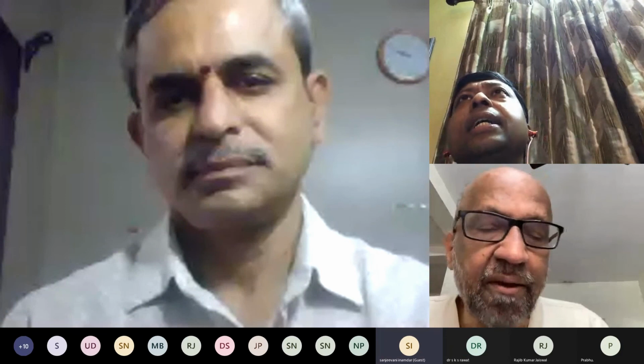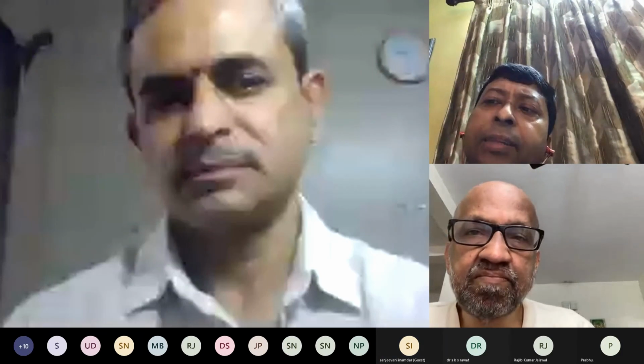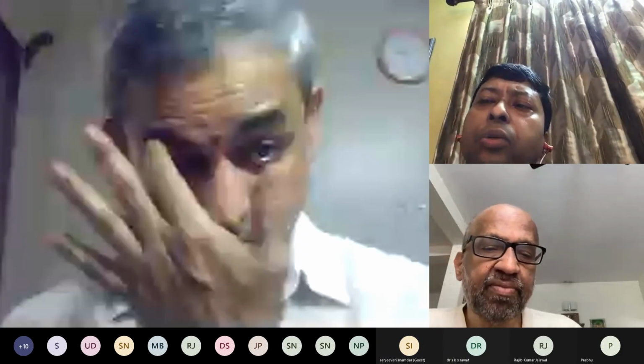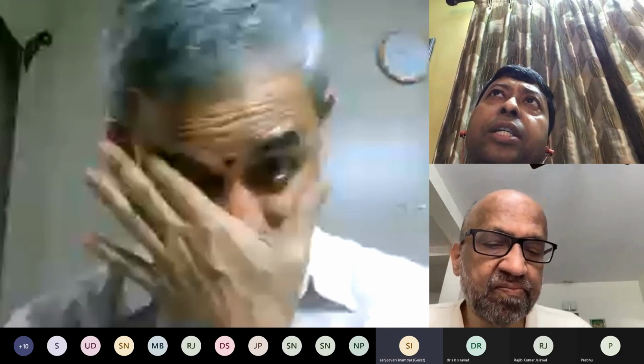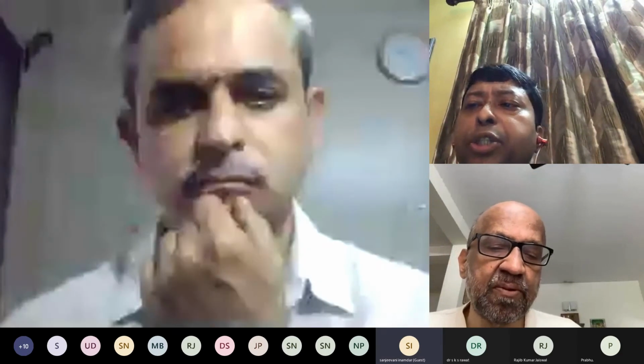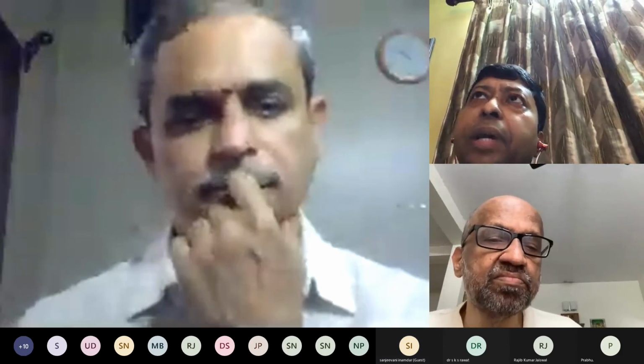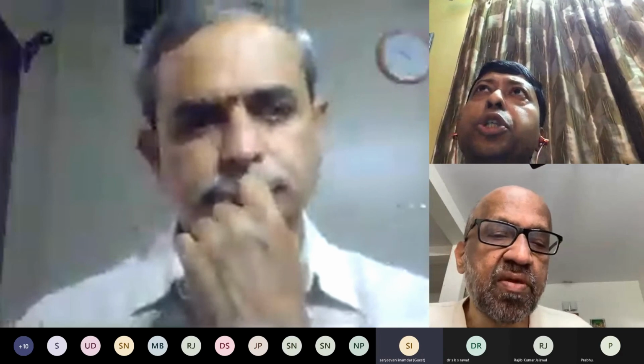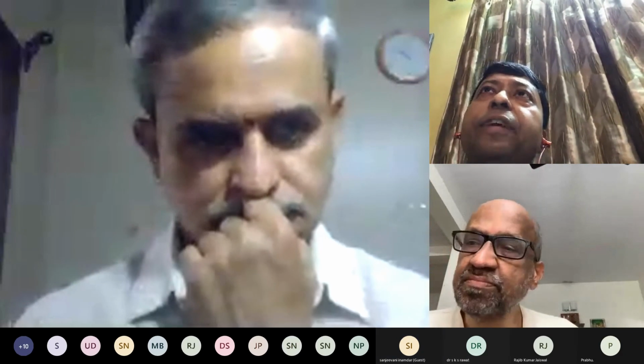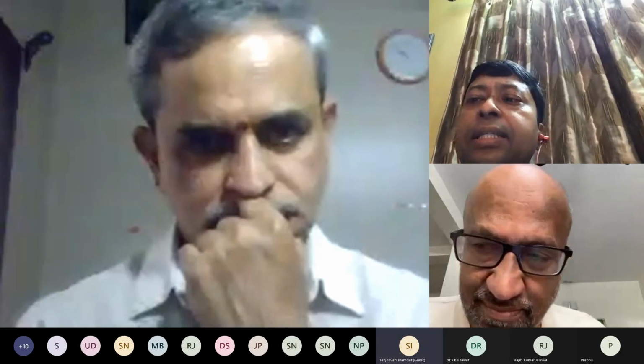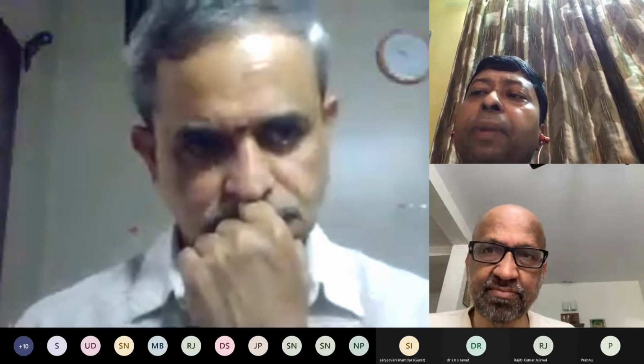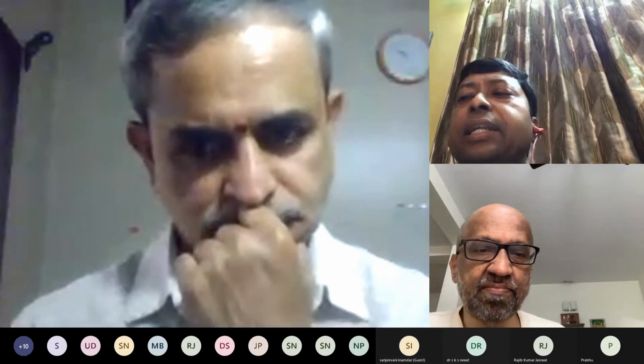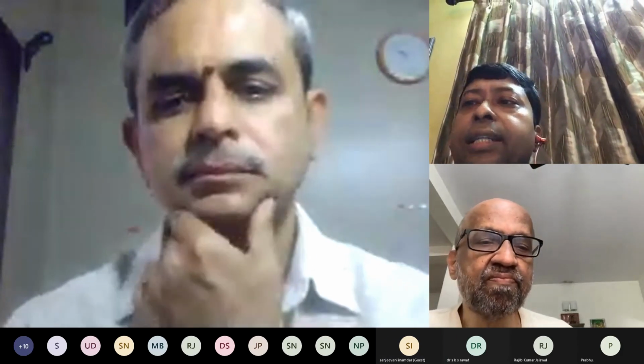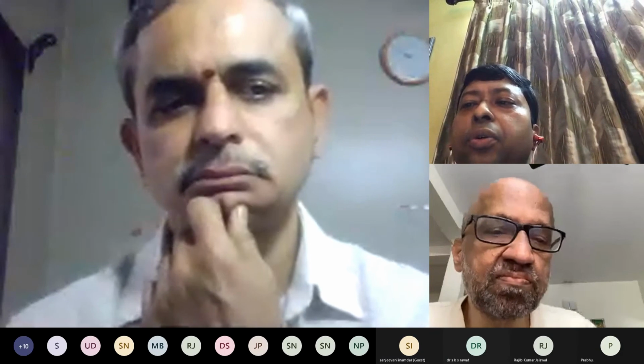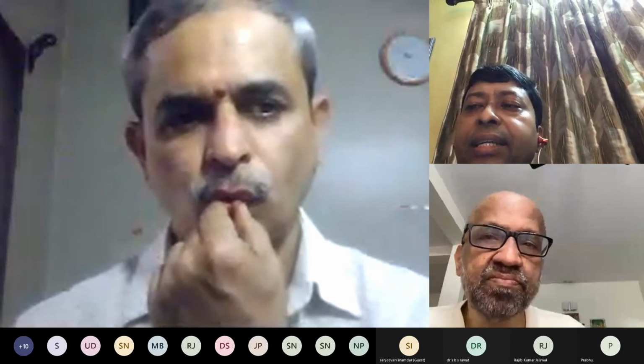Yes, ma'am. That is kind of self-explanatory because the entire calculation of valve areas is based on the Doppler principle and the Doppler shift. So if we artificially ensure that my transmitted frequency and the received frequency are the same, the Doppler shift will be entirely miscalculated and we will not get the adequate area. So that cannot be applicable in that area. Yes.